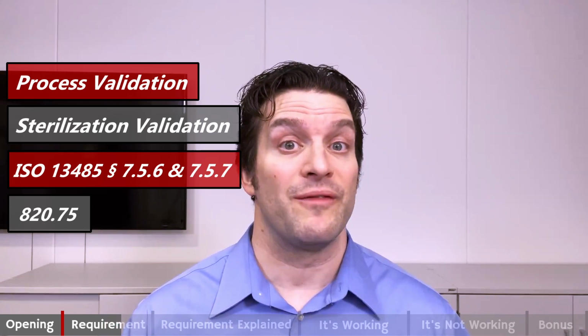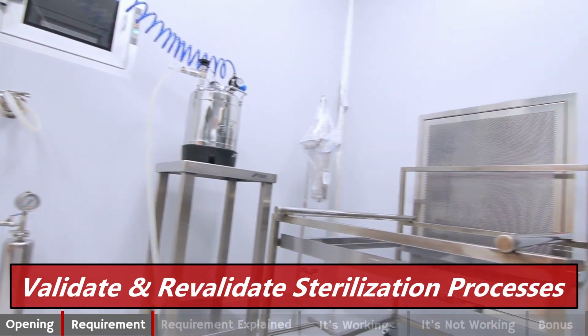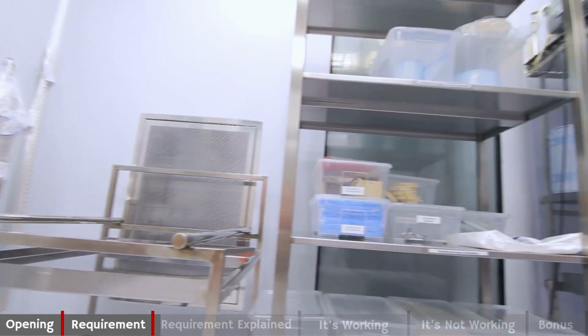Our topic, sterilization validation, comes directly from 13485 section 7.5.6 and 7.5.7, and 820.75. Sterilization validation in five words: validate and revalidate sterilization processes. If our medical device is sterile, we have to ensure that we have a validated sterilization process for our medical device. Within the medical device industry, there are common sterilization processes that happen to fall in what the FDA calls Category A, and those are radiation, so gamma and E-beam, ethylene oxide, autoclave or heat, and then moisture or steam.